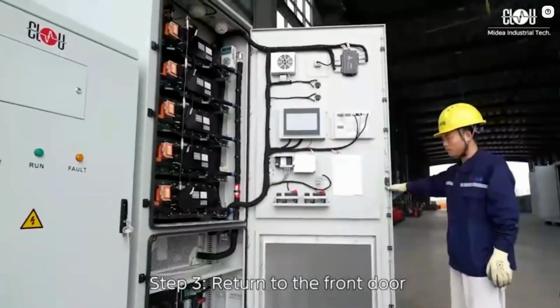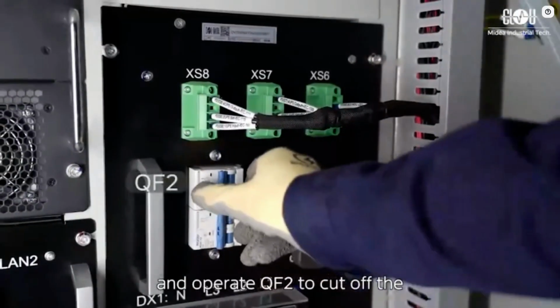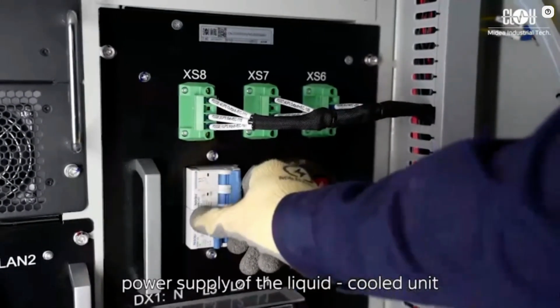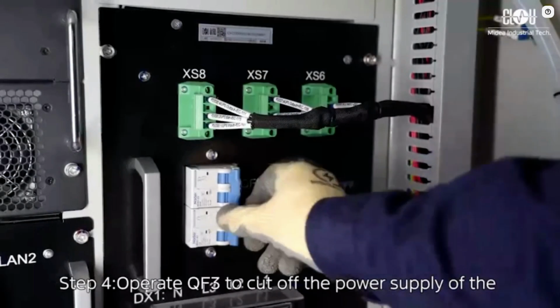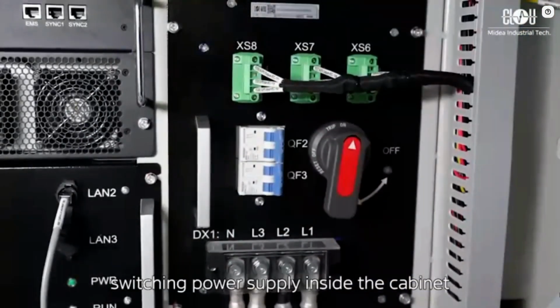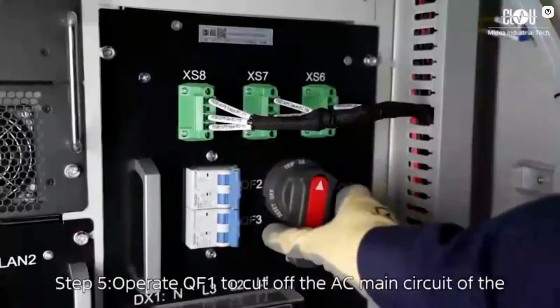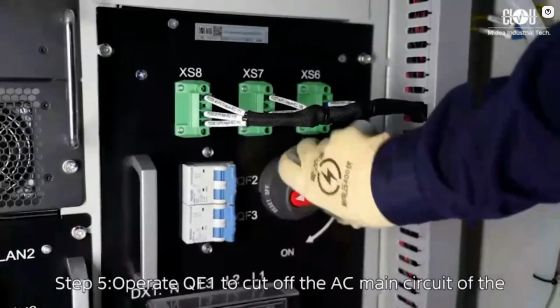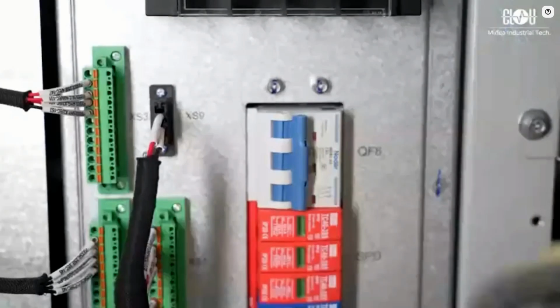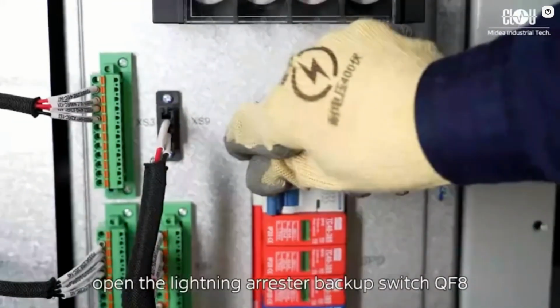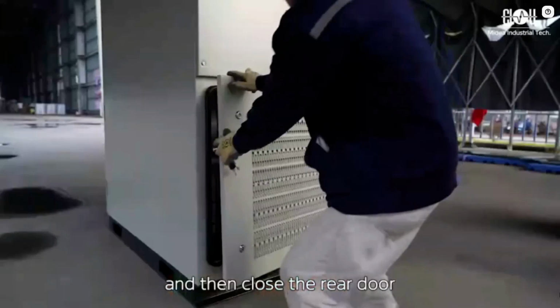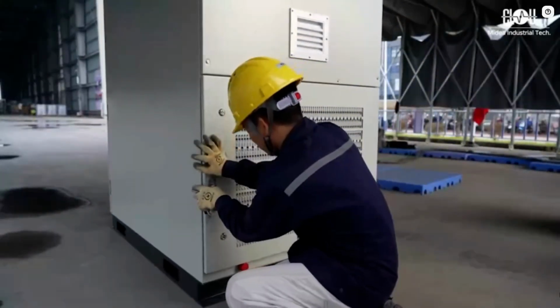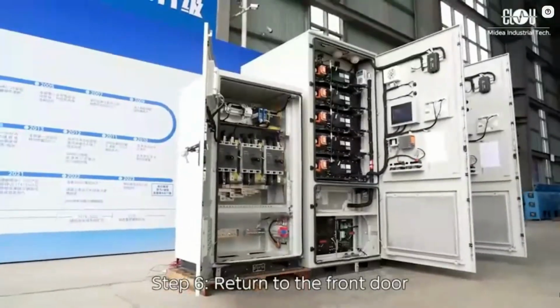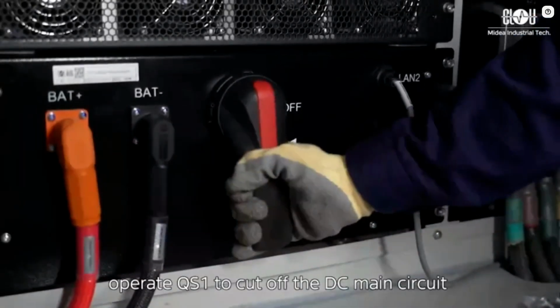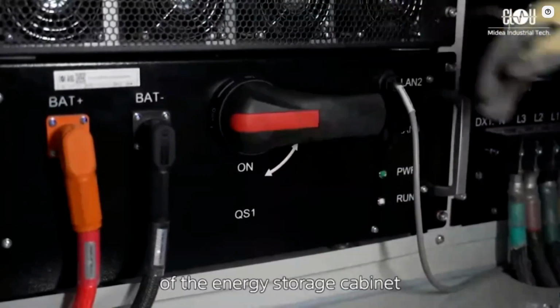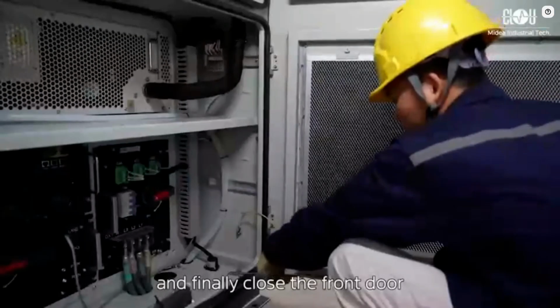Step 3. Return to the front door and operate QF2 to cut off the power supply of the liquid-cooled unit. Step 4. Operate QF3 to cut off the power supply of the switching power supply inside the cabinet. Step 5. Operate QF1 to cut off the AC main circuit of the energy storage cabinet. Return to the rear door, open the lightning arrestor backup switch QF8, and then close the rear door. Step 6. Return to the front door. Operate QS1 to cut off the DC main circuit of the energy storage cabinet. And finally, close the front door.